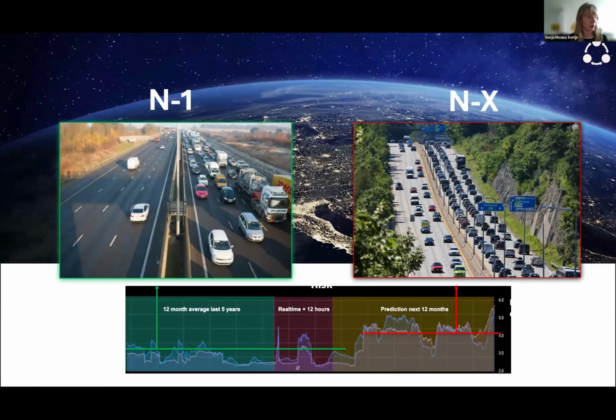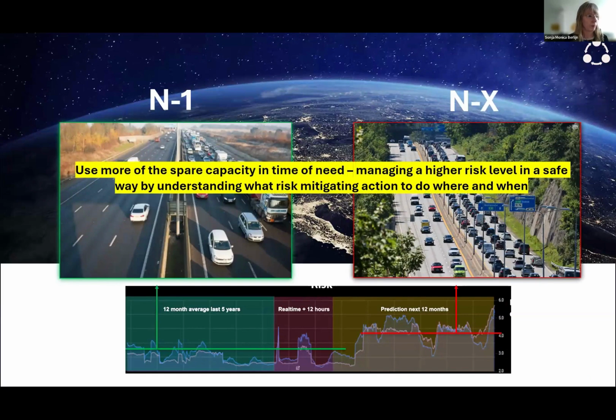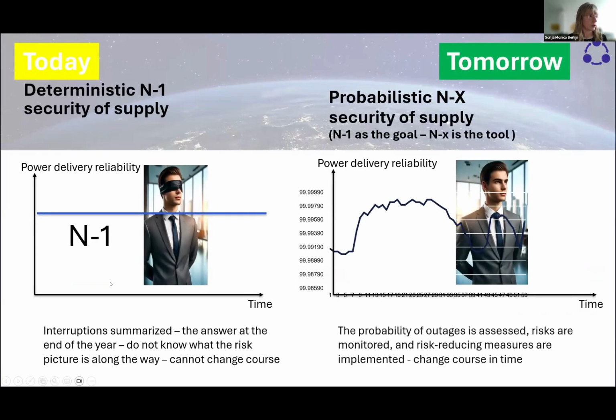So this is about going from N-1 to N-x: we can use much more spare capacity if we manage the risk that we have, because risk is a function of the probability of something happening and the consequence of that event. And now with new technology, we can actually reduce the consequence of an event, and that's why we can allow a little bit higher probability for something to happen. But these principles haven't been updated, you could say. So nowadays there are measurements and software available to actually calculate the actual risk. That's why I would like to challenge the idea of running a system blind and just thinking that you have N-1. You should plan and build for N-1, but maybe not operate according to N-1.